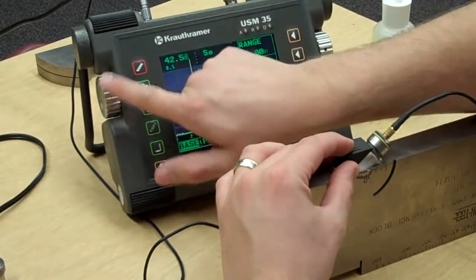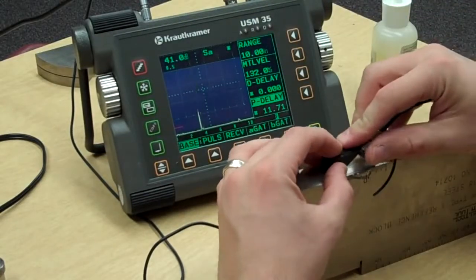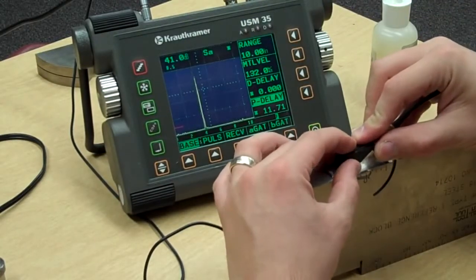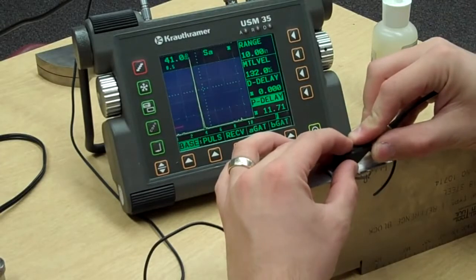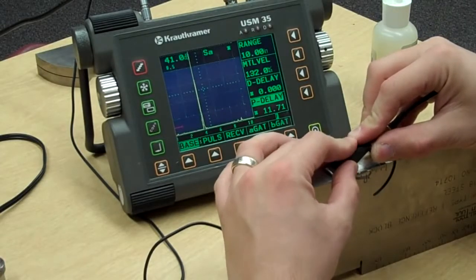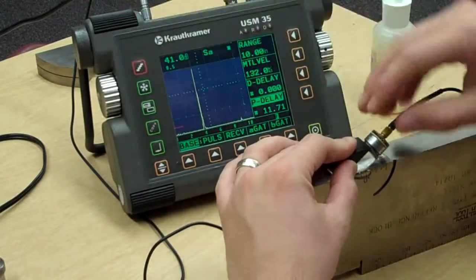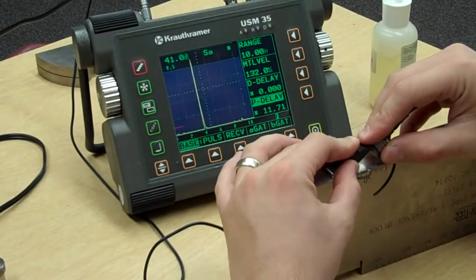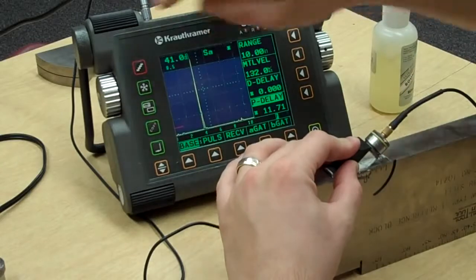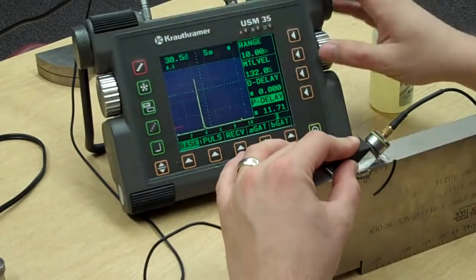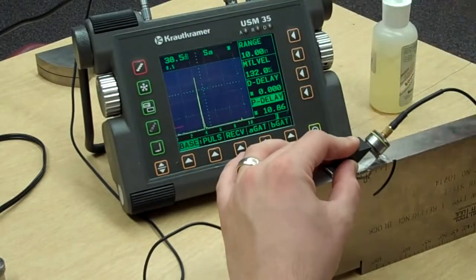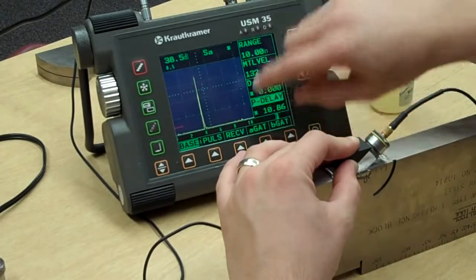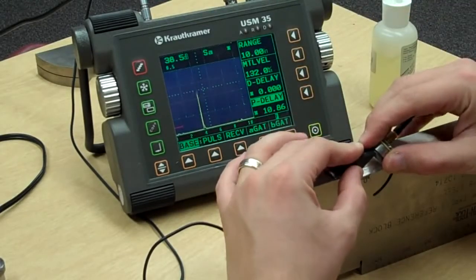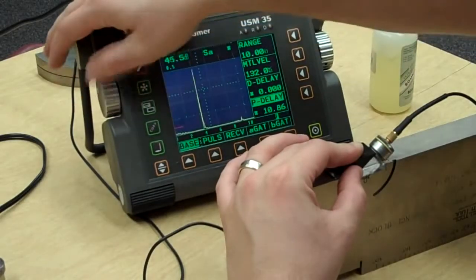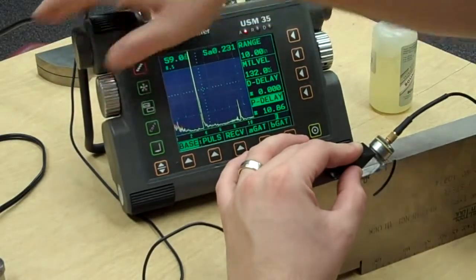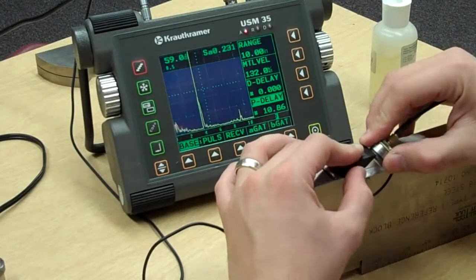Okay? I'm going to bring my gain down a little bit so I can see the top of that signal, because I want to move this back and forth and peak that signal out. Okay, so there it's pretty much peaked out. And that is what I want to control my calibration off of. So I'm going to back it up just a little bit. And now I should have a signal over here about 9. If I bring this over a little bit, that helps it stand out a little more. Bring up my gain. I'm pretty close to 9.